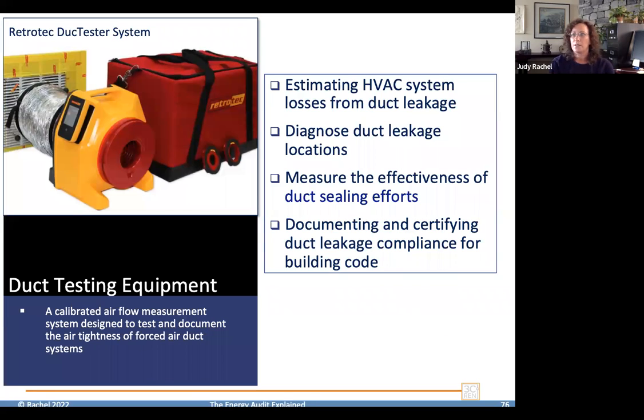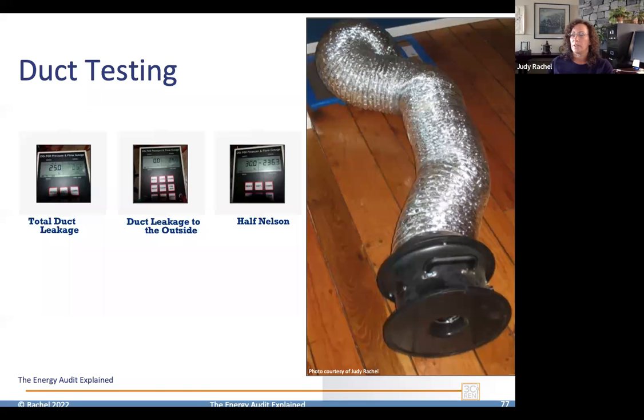Then there's the duct testing. Once again, RetroTec and Energy Conservatory are the 2 companies that make duct testing equipment. Next month, there will be a webinar on duct testing, so you might want to take a look at that webinar. And the duct test is more than just duct testing. It actually tests the whole distribution system, which is the air handler through the entire duct system out through the grills. It's any leakage throughout that whole system. The three basic tests are total duct leakage, duct leakage to the outside, and the half Nelson, and those will all be talked about in detail in the duct testing webinar next month.